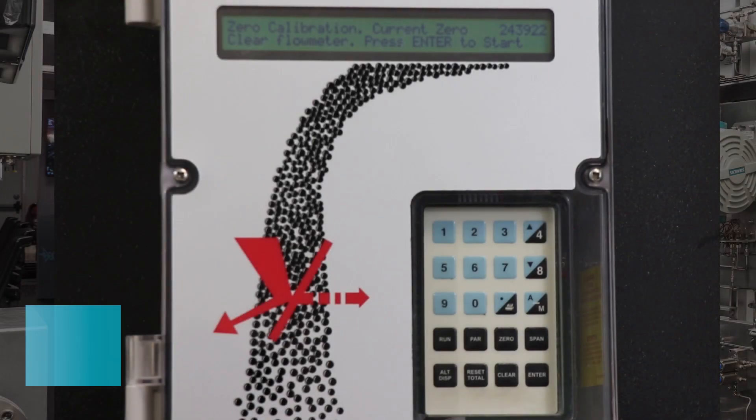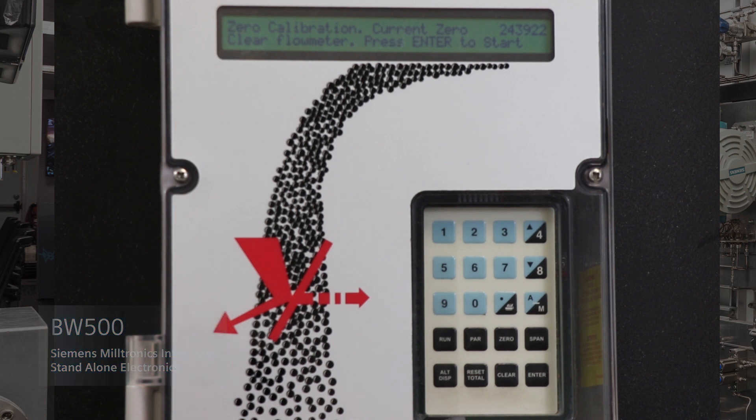The first thing you'll want to do is make sure the unit zeros. If the unit is new and you're calibrating it for the first time, it will force you to do an initial zero. Then you will hit the enter button. It will start the zero calibration and you can see from the screen that it is counting up. When the calibration is finished, it will return to zero and you will hit the enter button to accept that value.